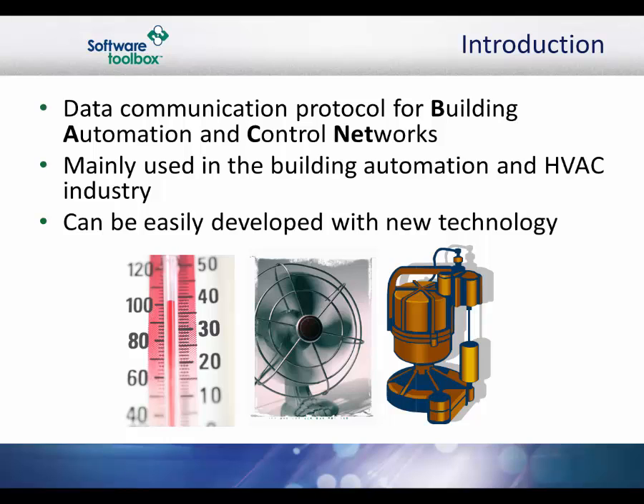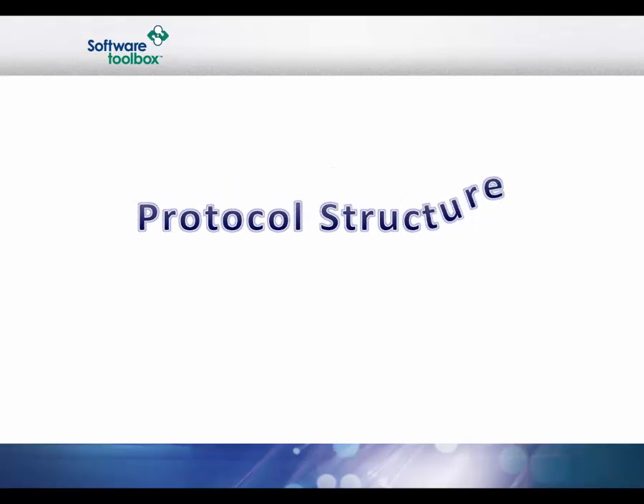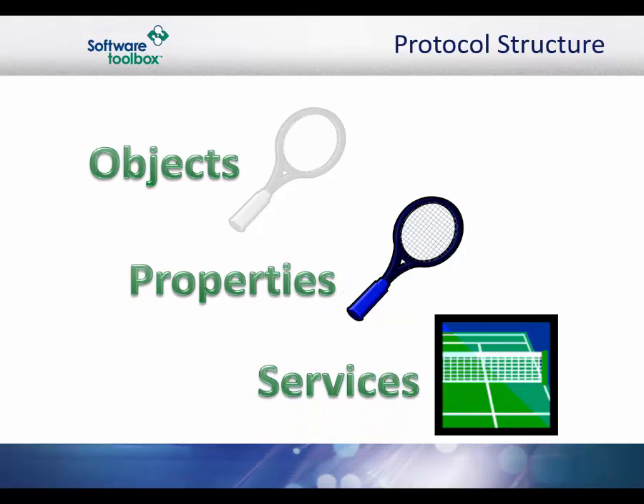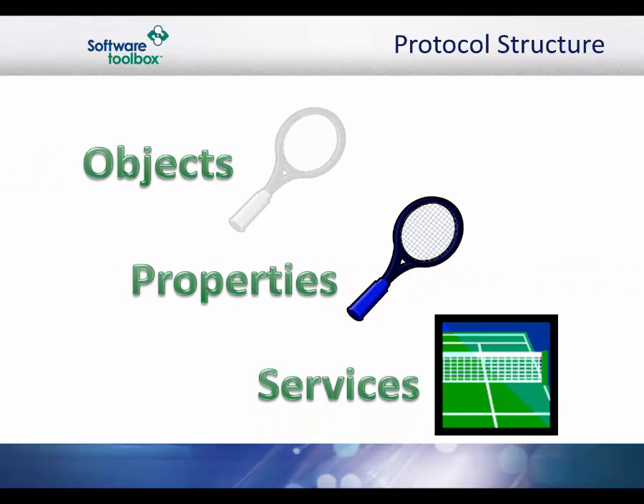If a vendor creates a new functionality for which communication is required, the vendor can add new properties to existing object types, or create new object types that are accessed in exactly the same way as the ones defined in the standard. BACnet specifies most of the common functions in order to remain applicable to almost any kind of monitoring or control application. The main components of the protocol include objects, properties, and services. An object is simply a collection of information related to a particular function that can be uniquely identified and accessed over a network in a standardized way.